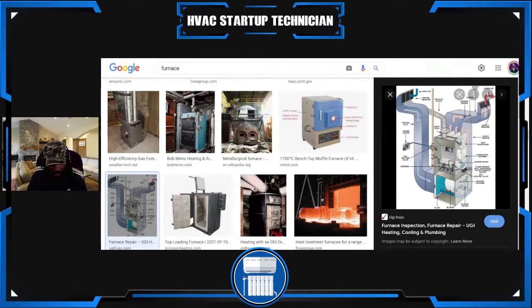I have to talk about BTUs again, because you can also work out your BTUs outside. Every 12,000 BTUs, you need 400 CFM. So every ton, you need 400 CFM. Think about that, right? If you have a 1 ton unit outside, you need 400 CFM. If you have a 2 ton unit outside, you need 800. Do you understand? It goes by that.